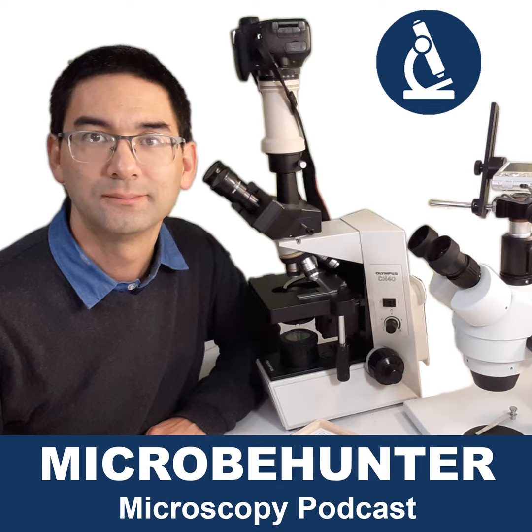And when you use those objectives, you get a larger field of view, also a larger depth of field, and also a little bit more image brightness. And this actually might be better than using a higher magnification, which gives you a higher resolution, but you have other problems, okay? So you might go for a lower magnification first, okay?